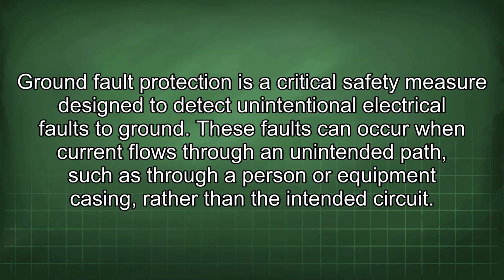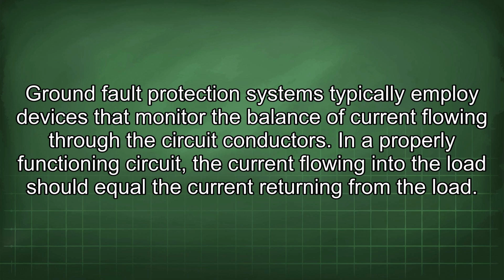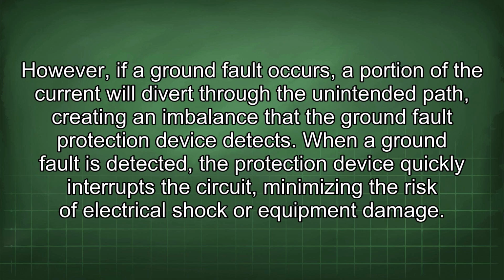Ground fault protection is a critical safety measure designed to detect unintentional electrical faults to ground. These faults can occur when current flows through an unintended path, such as through a person or equipment casing, rather than the intended circuit. Ground fault protection systems typically employ devices that monitor the balance of current flowing through the circuit conductors. In a properly functioning circuit, the current flowing into the load should equal the current returning from the load. However, if a ground fault occurs, a portion of the current will divert through the unintended path, creating an imbalance that the ground fault protection device detects.